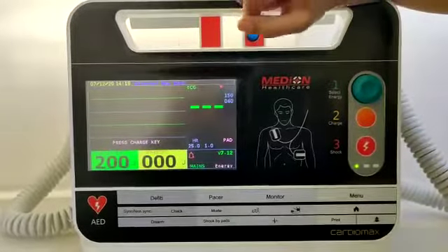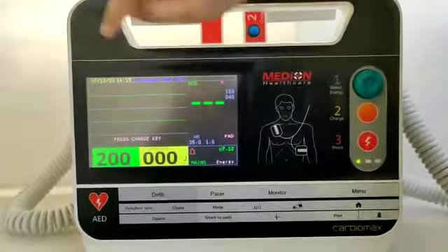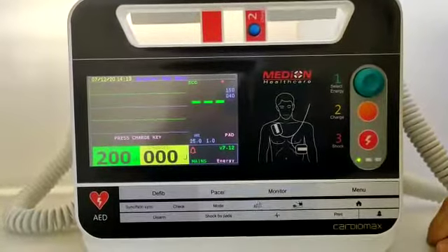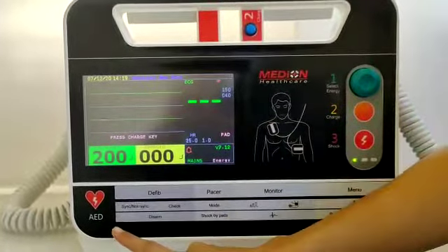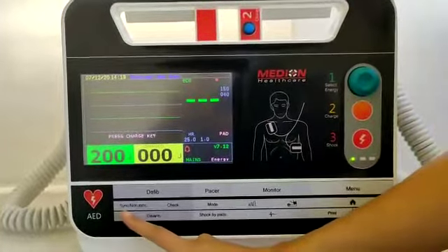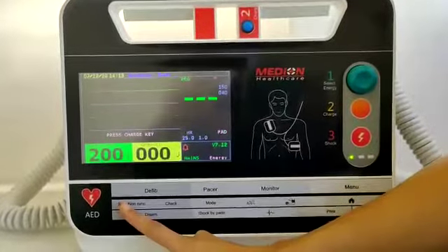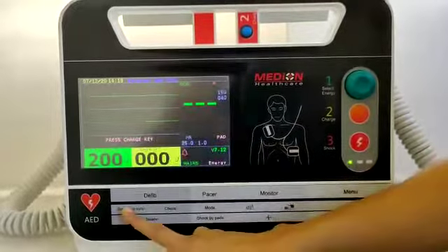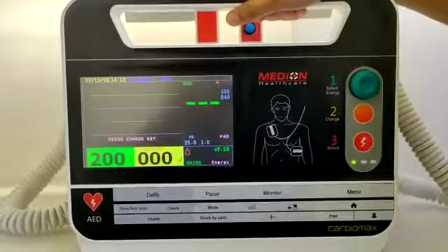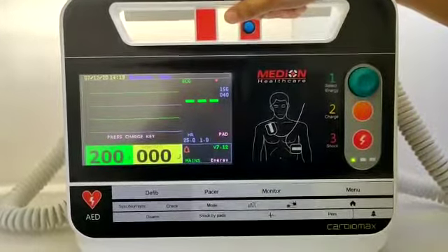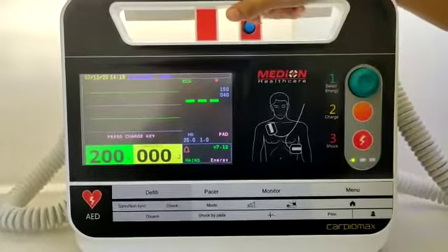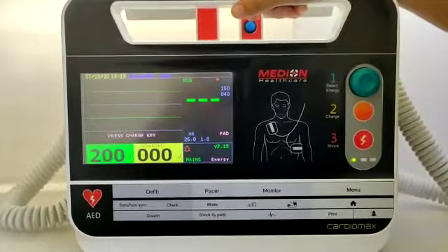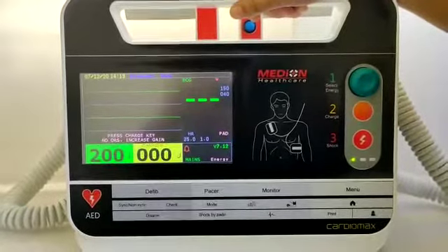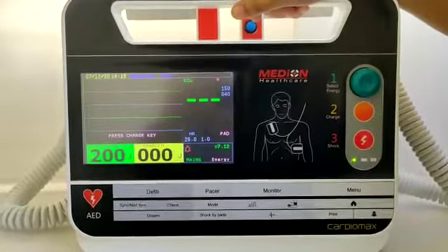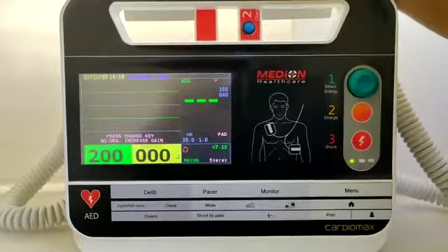Next is the defibrillation mode, defib mode. When the defibrillator is engaged in the defib mode, there are two operational modes, sync and non-sync. It will be seen over here, external sync, external non-sync. In sync mode, the defibrillator will sync with the R wave of the patient's QRS wave and will deliver the shock after 60 milliseconds. Whereas in the non-sync mode, there will not be any synchronization. Shock will be delivered anywhere in the cardiac cycle.